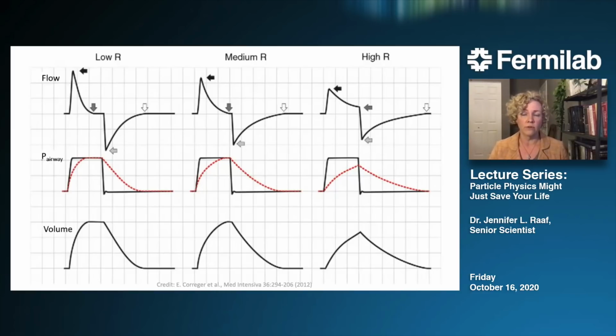So you'll remember from that equation what the airway pressure is. And in this case, it's just a square wave because it's a pressure controlled ventilation. So we're providing a fixed pressure during the inhalation, and then we remove it during the exhalation. The red dashed line is showing you the pressure of the alveoli in the lungs. And as you go to higher resistance, moving to the right, that pressure is reduced, and the curve broadens out. It takes longer to get back to the minimum baseline pressure.